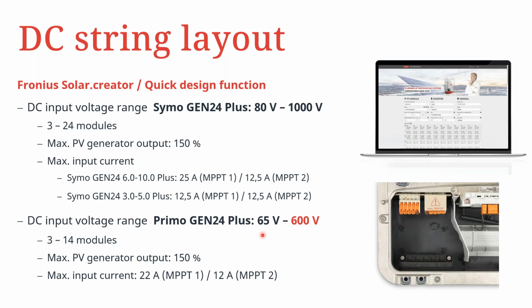For the Primo GEN24 Plus, the voltage range is 65 volts to a maximum here of 600 volts. So we can see here also we have quite a big difference between the Symo and the Primo GEN24 Plus. And therefore it means for the module configuration, we can start from a string of 3 modules to a maximum of 14 modules per string. But the over dimensioning can be achieved also to a factor of 150%.